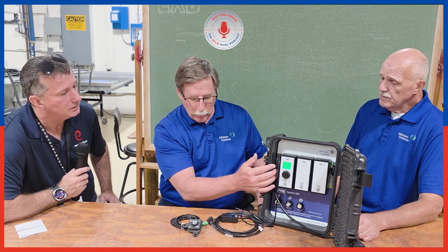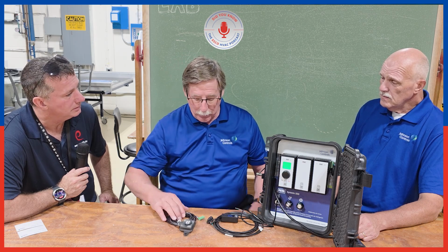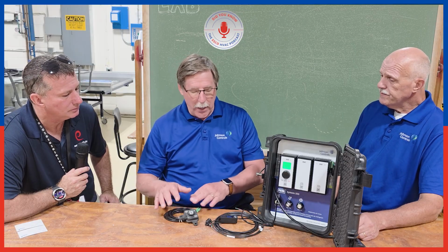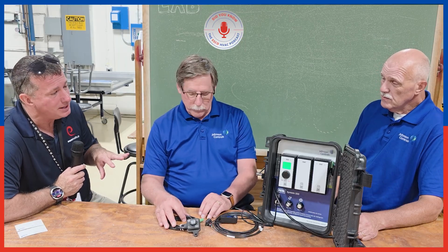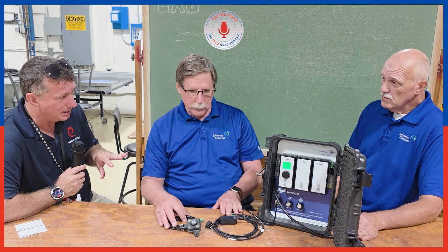What I mean by full capabilities is that the controller and the sensor, and this is an example of the sensor, in combination are considered an RDS, or refrigerant detection system. Absolutely. So they have all of the requirements under UL 60335, both -2-40 and -2-89, to qualify as an RDS. So technically this could even be used in a residential style application if need be. Correct. Wow. And so with the modular, now I'm starting to see what you meant by modular. So this is actually a full control network, and it's expandable for the amount of outputs that we would need to control.